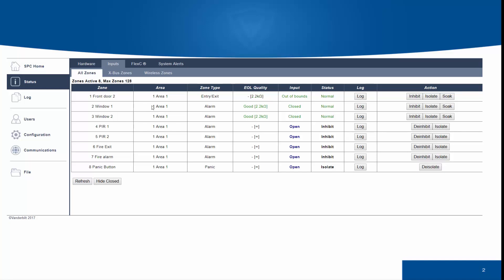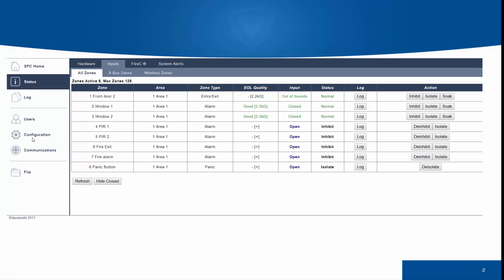Other items you may see in this status menu may be unstable. Unstable occurs when the SPC system is unable to get a valid sample from the zone. Generally, this is down to poor wiring or interference on the line.